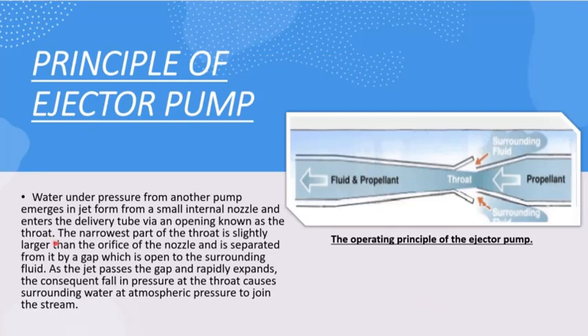Next, let's learn about the working of an ejector pump. An ejector pump works based on the Venturi effect. The Venturi effect is the reduction in fluid pressure that results when a fluid flows through a constricted section of a pipe. When water is forced through the narrow section of a pipe, it increases in velocity and there is a corresponding reduction in pressure in that region.